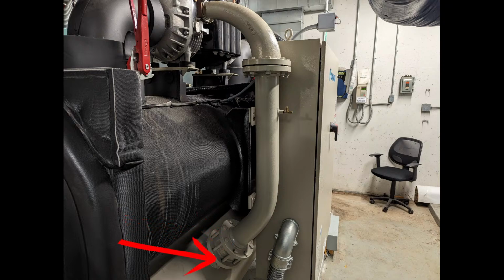So basically, the check will open some as a relief. It will relieve the pressure that had built up, and it's going to slam shut. Now, this happens very rapidly, and it's where you'll hear this clank, clank, clank, clank, clank, clank, and it kind of just smooths out as the compressor is able to get up to speed. That hammering that you're hearing was causing a lot of valve failures in the first and early generations.